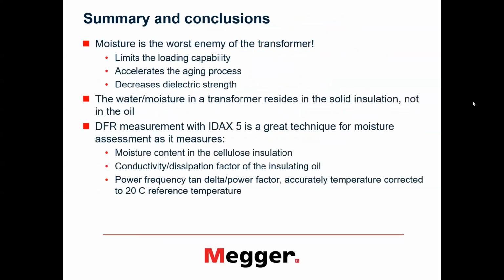And if we just summarize and conclude, what I have been telling is that moisture is something we want to avoid in power transformers. It will limit us in the loading capability of the transformer. It will make the transformer age faster, and electric strength will go down. And since water resides in the solid insulation, DFR with IDAX is quite a great technique to assess this moisture content by doing tangent delta measurement at a wide frequency range. Yeah, that would be all I was about to say.